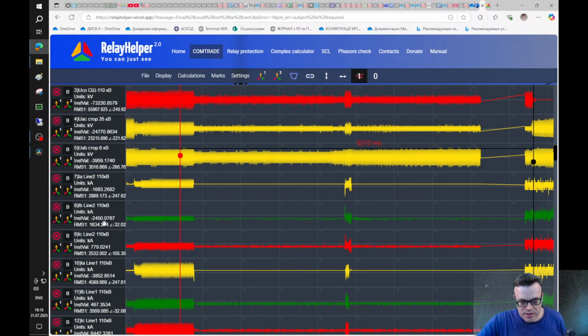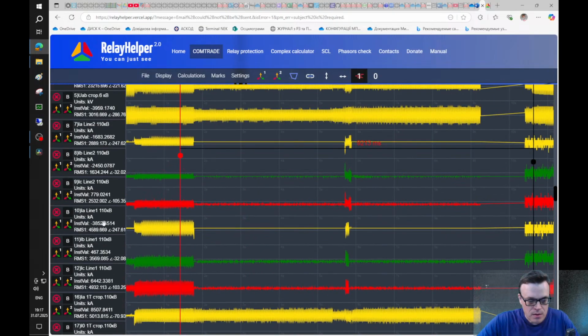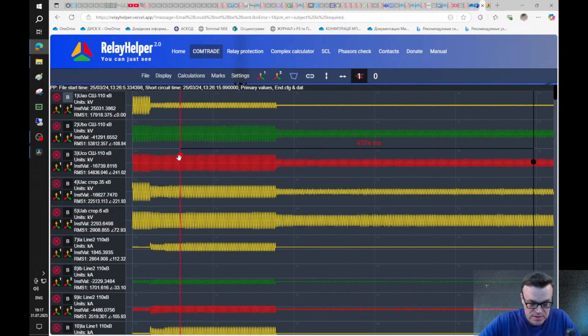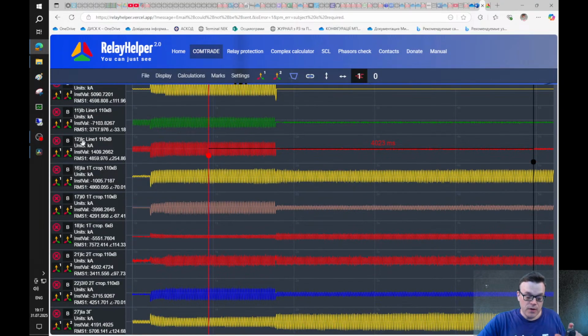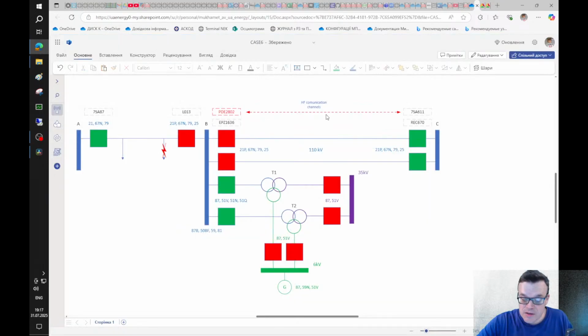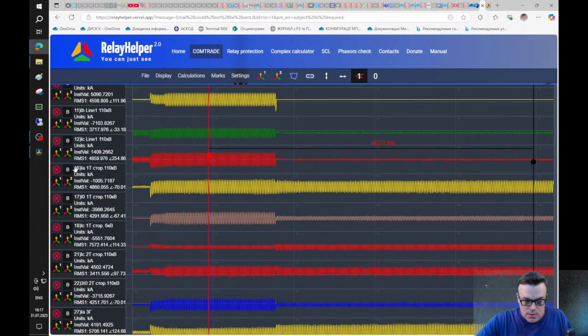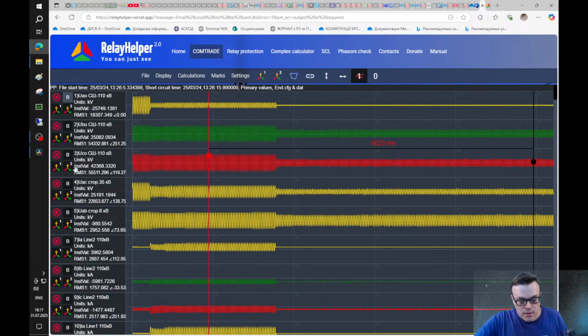We started investigation by calculating zero sequence current. You can see that the fault is a single phase short circuit on the phase A, because we have zero sequence currents of transformer, so we can calculate what zero sequence current was flowing on that line. As I said, we found that was a single phase phase A to ground short circuit, and we need to calculate zero sequence parameters, zero sequence voltage and zero sequence currents of all lines.